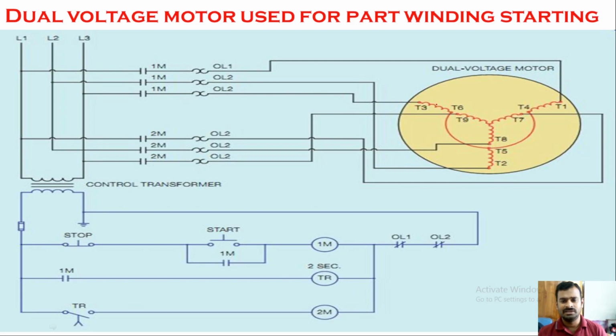Here you will have only this coil, so the coil resistance will be higher, and when the time delay has lapsed, the second contactor will be turned on. So coil 1 and coil 2 will be connected in parallel. The resistance will drop, so the current can increase, and by that time the torque requirement can also be achieved. That is how the dual voltage motor is connected for part winding starting. Actually, I have discussed this particular topic in our previous video. If you have any doubt, please check that video. So this is a dual voltage motor used for part winding starting.